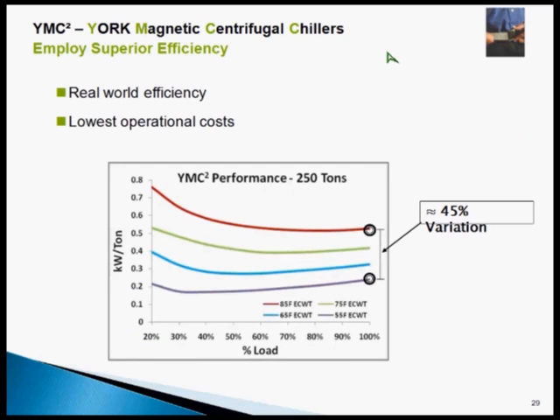This is the hottest day of the year. Remember we talked about the cooling towers? This red line is the hottest day of the year. That's when your cooling tower is making its design temperature. That's it. Many, many other days of the year in Pittsburgh, it can make 75, 65, and 55. The cooling tower that was designed for the worst day of the year, sitting out there on your building in Pittsburgh, can do much better than that on a typical day. So let's just call it right in here.